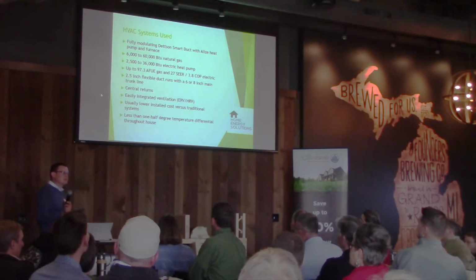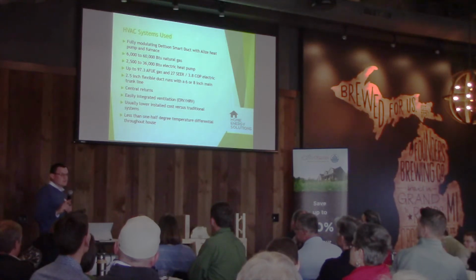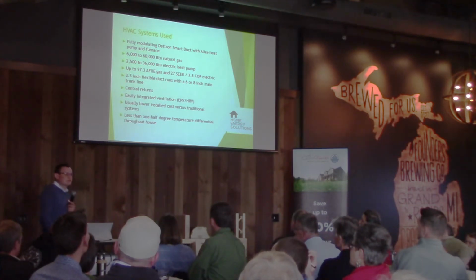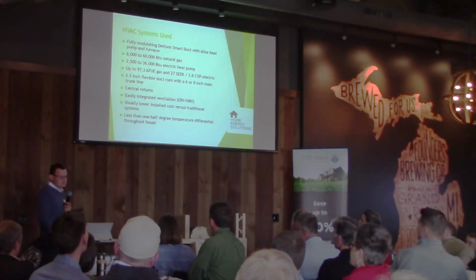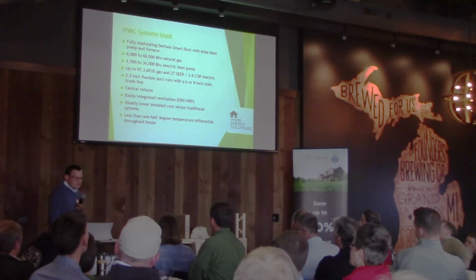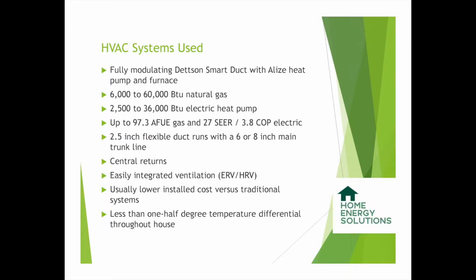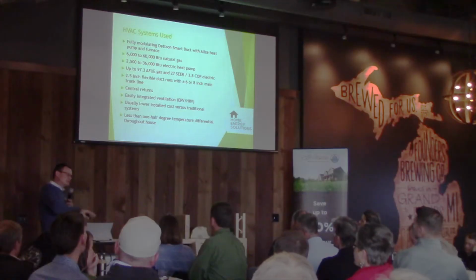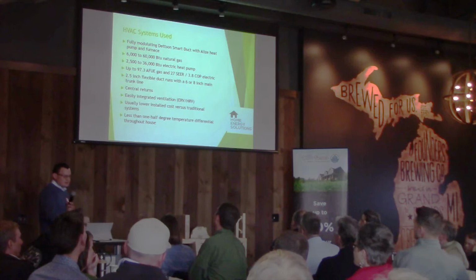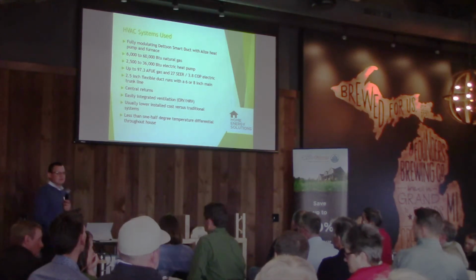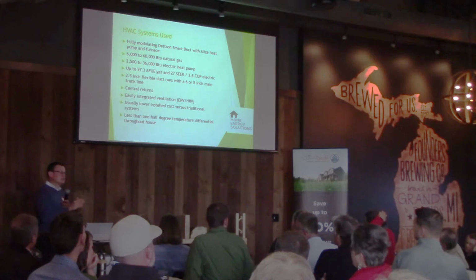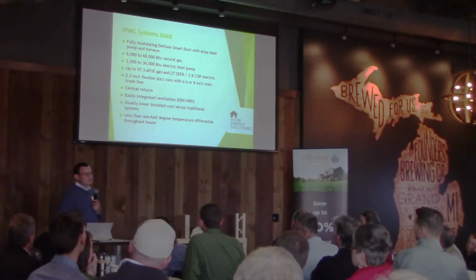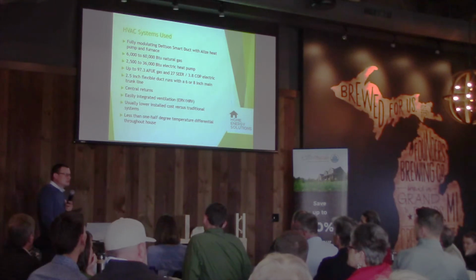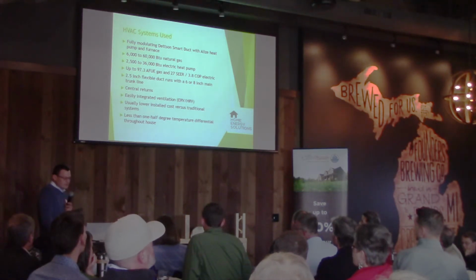But when we're down into those low loads, even a 4-inch or even a 3-inch metal duct, which is about the smallest you can get without having it custom fabricated, is way too big to deliver airflow throughout a house. On the heat pump side, these systems are up to 27 SEER and a COP of about 3.8. And like they were saying, your COP does go down the farther down that you go. But these numbers are based on all of the standards that they do for certification, so you can compare apples to apples. But I can guarantee you when it's 5 degrees outside, you're not going to get 3.8 out of it. You're probably going to be down at around the 2 range, maybe 1.82.